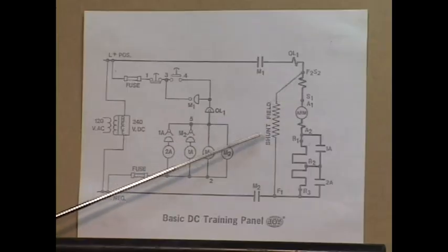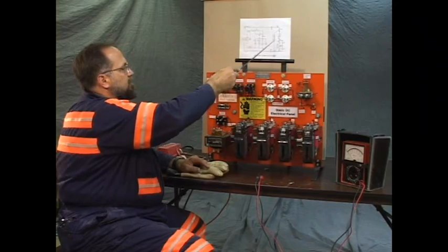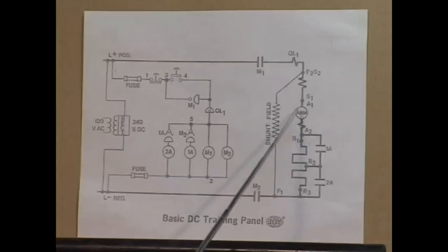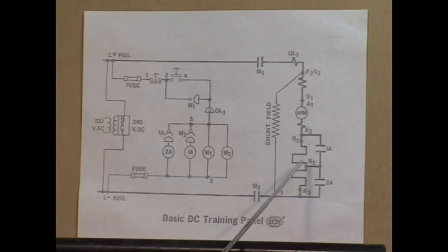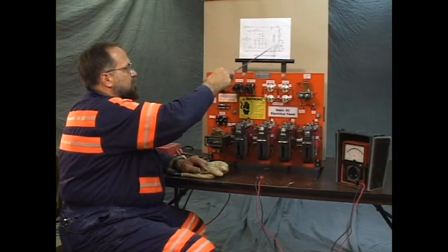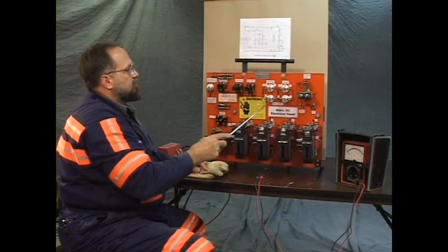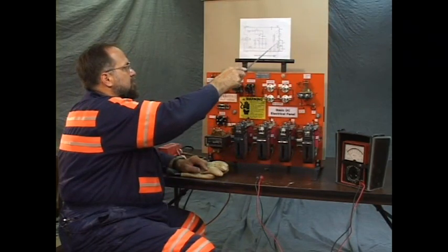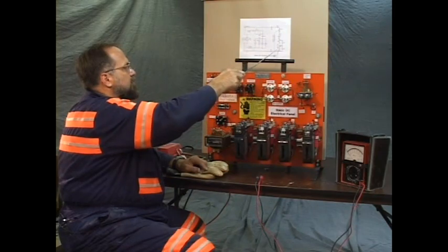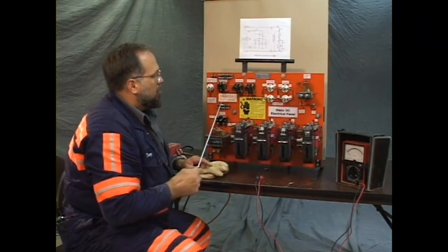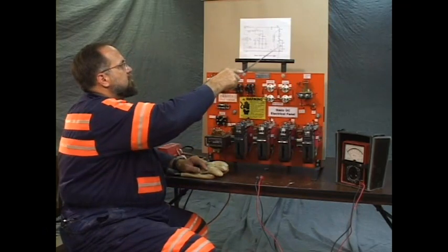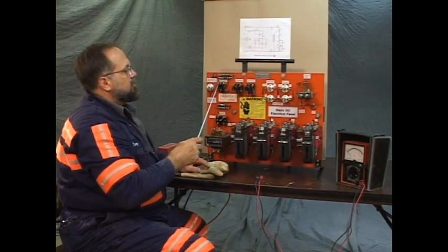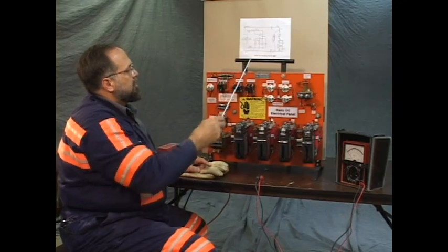The shunt field light is on a separate branch. It's immediately at full power. The armature, the light between R1 and R2, the first stage resistance, and the second stage, share this branch. And with the power being divided between 3 loads, these 3 lights are dim. Armature, the light between R1 and R2, light between R2 and R3. We can refer to them as the 1A resistor or the 2A, and that would make it easier to reference.